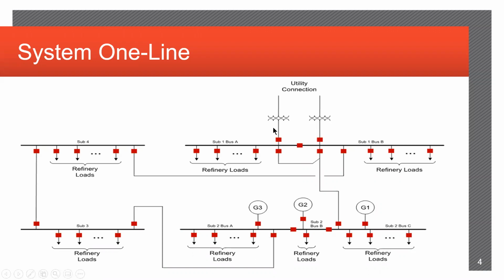I believe it was a decision of the refinery themselves that they didn't want to go with a frequency rate of change element in order to detect an island. And so it is absolutely purely based on circuit breaker status. And this, like I said, there were 17 circuit breakers. You can see there's these 5 here, this number 6, 7, 8, 9, 10, 11, 12, 13, 14, 15, 16. I think I miscounted, but there was a total of 17 circuit breakers that made up the entirety of the logical determination.